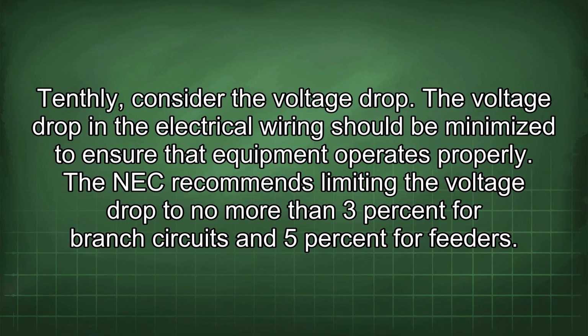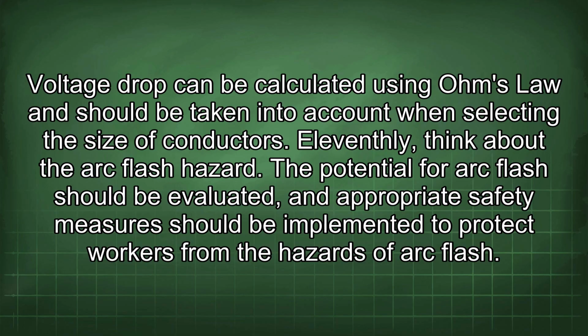Tenthly, consider the voltage drop. The voltage drop in the electrical wiring should be minimized to ensure that equipment operates properly. The NEC recommends limiting the voltage drop to no more than 3% for branch circuits and 5% for feeders. Voltage drop can be calculated using Ohm's law and should be taken into account when selecting the size of conductors.